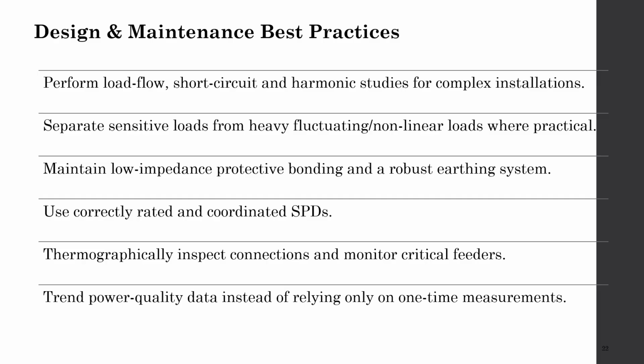Design and maintenance best practices. Perform load flow, short circuit and harmonic studies for complex installations. Separate sensitive loads from heavy fluctuating nonlinear loads where practicable. Maintain low impedance protective bonding and a robust earthing system. Use correctly rated and coordinated SPDs. Thermographically inspect connections and monitor critical feeders. Trend power quality data instead of relying on one-time measurements.